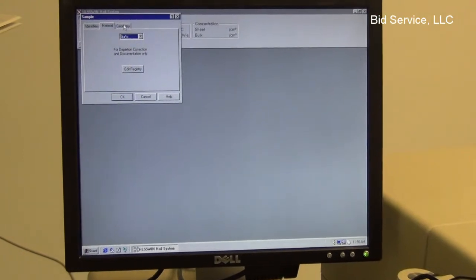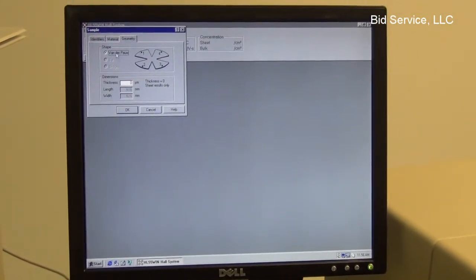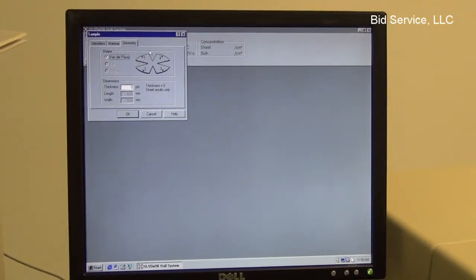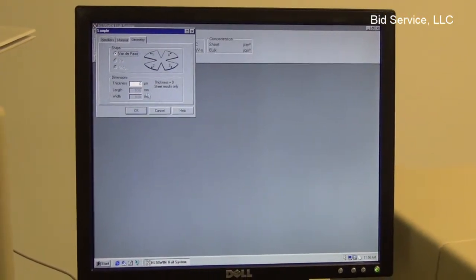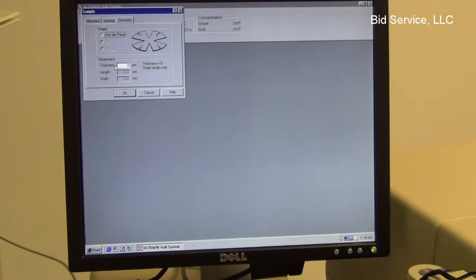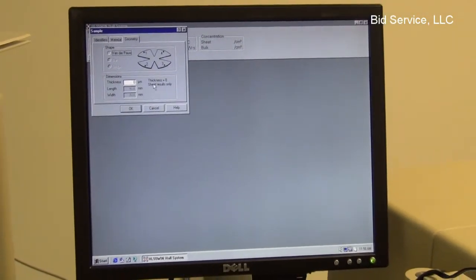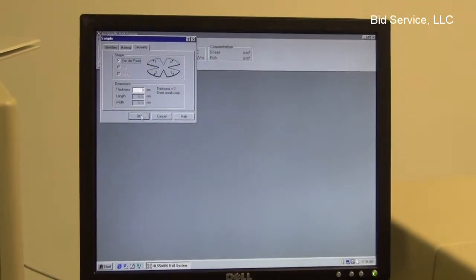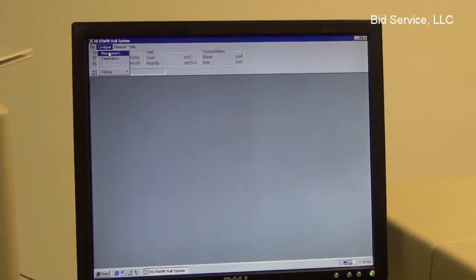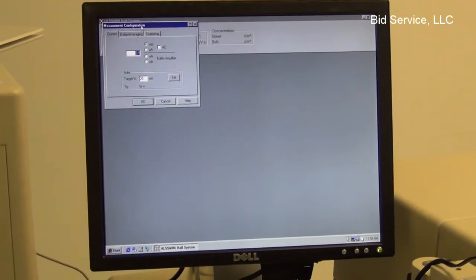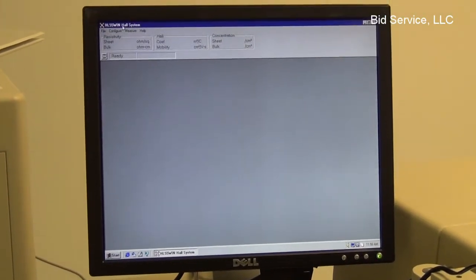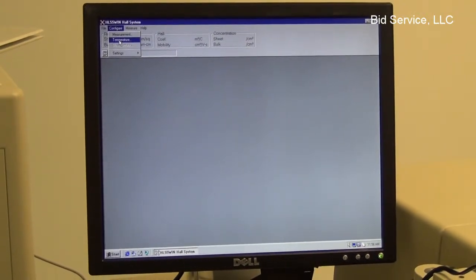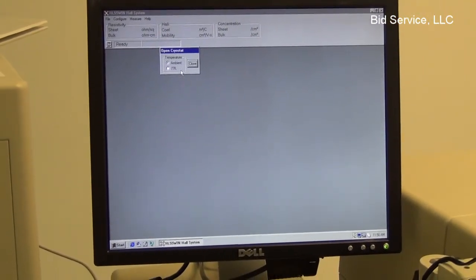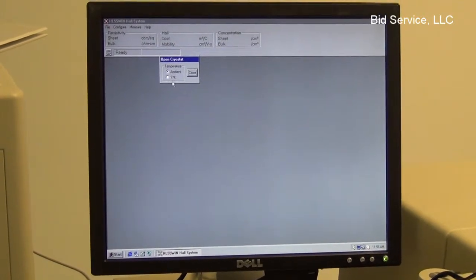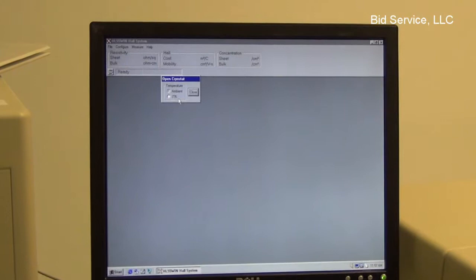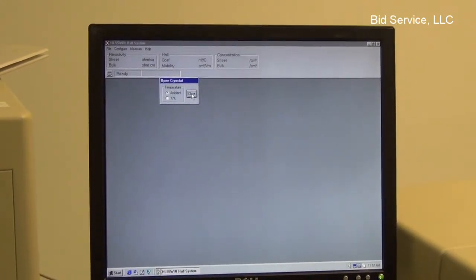And then the geometry is Van der Pauw geometry, four probes. And in case the bulk properties of the unit are to be measured, we have to enter the thickness of the sample here. For sheet results, the thickness should be zero. Now the configuration is the second menu item. Here, there is a temperature submenu. We can select ambient, or if there is liquid nitrogen in the reservoir, you can use 77 Kelvin temperature.